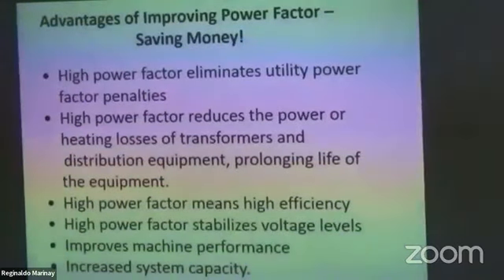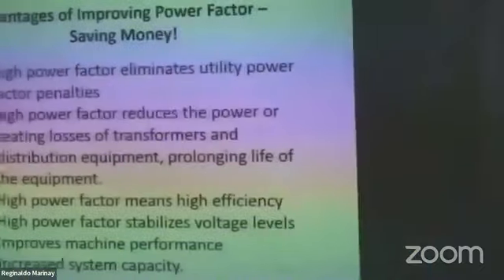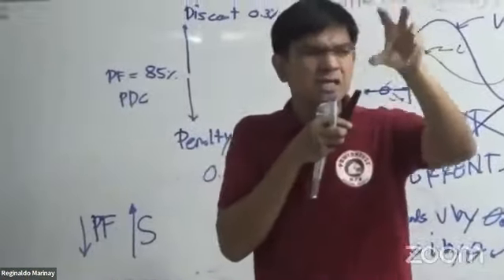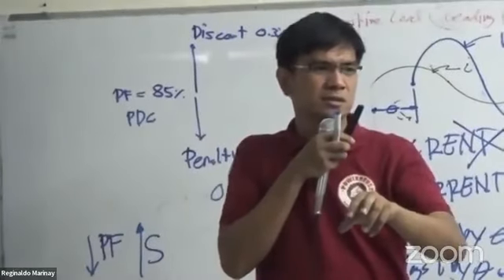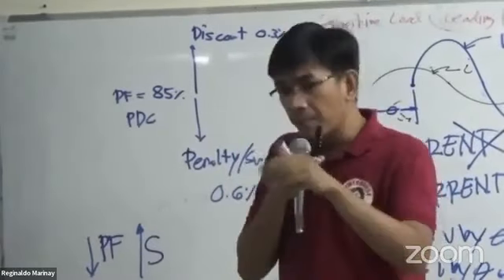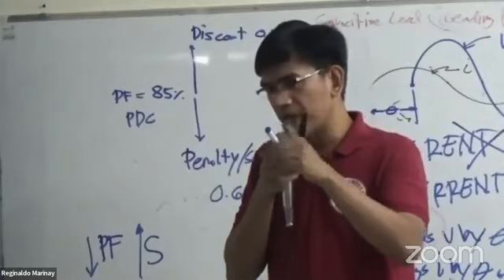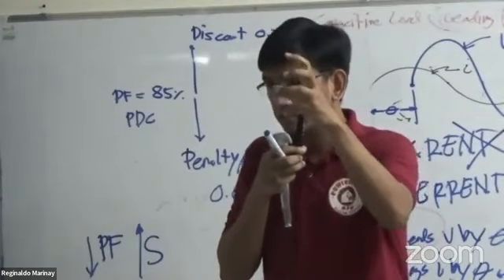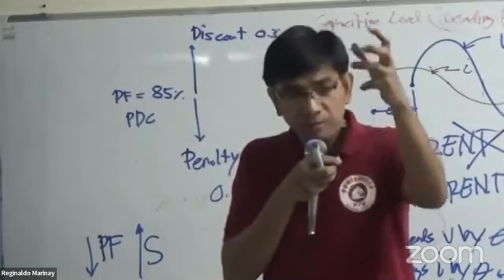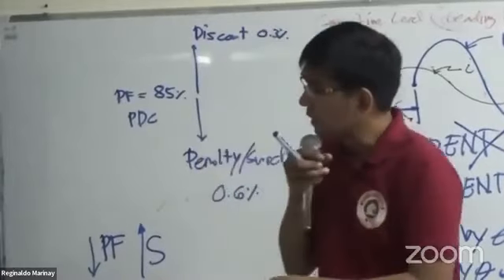And other equipment too - the heating losses of your transformer, generators, your equipment. If you have a high power factor, it won't heat up as much. The lower the power factor, the more heat it will generate. Your equipment will generate more heat for a lower power factor.